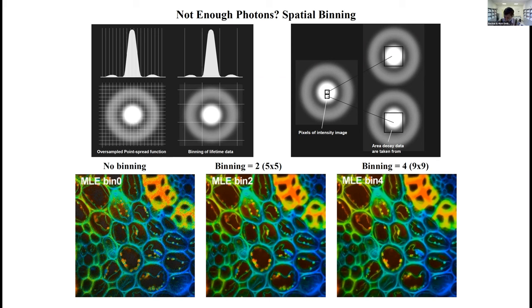To get a good image, the rule is that the point spread function needs to be oversampled. The rule is it should be sampled by something like five by five points. You do this automatically because an undersampled image looks ugly. So if you determine the lifetimes in all these pixels simultaneously, you get the same value because everything is mixed around by diffraction. We can bin this area. In SPCImage we do this by overlapping binning.